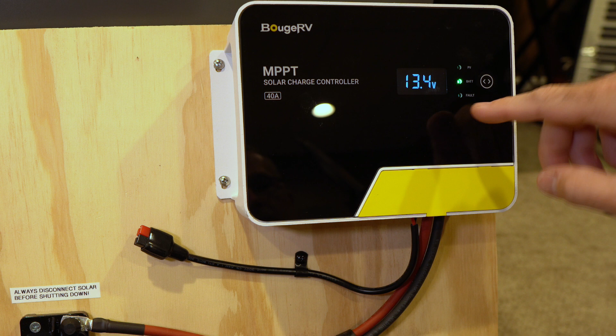Take that percentage with a grain of salt, because it's really calibrated for sealed lead acid batteries, which have a different voltage profile relative to state of charge than lithium ion does. So you typically shouldn't trust the percentage here—it'll often show 100% when in fact you're not. When you see this value, take it with a grain of salt.